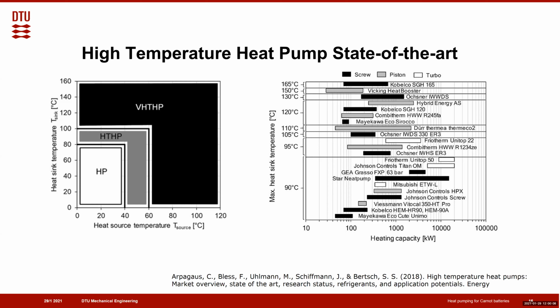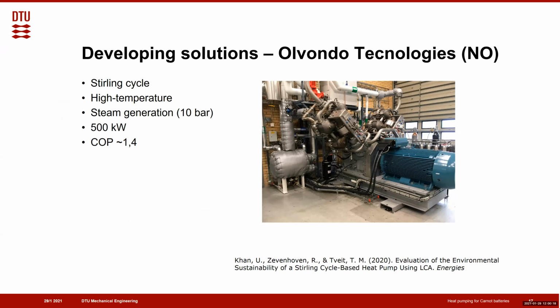Then there are technologies that are coming. One is this one from Norway, the Olvondo technologies. It's a Stirling cycle. They do have machines in operation for high temperature steam production, in this case in industry, reaching 180 degrees, 500 kilowatt capacity, and a COP of more or less 1.4, 1.3, 1.5, something like that.